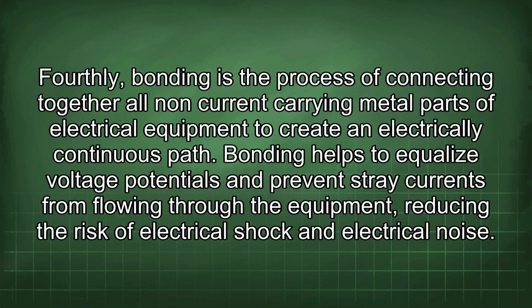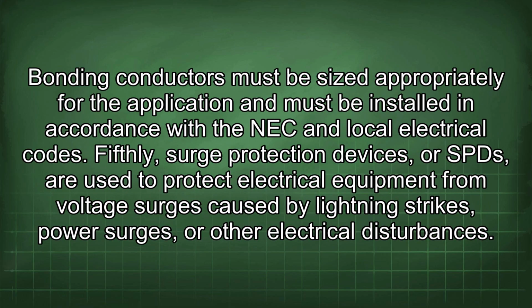Fourthly, bonding is the process of connecting together all non-current carrying metal parts of electrical equipment to create an electrically continuous path. Bonding helps to equalize voltage potentials and prevent stray currents from flowing through the equipment, reducing the risk of electrical shock and electrical noise.